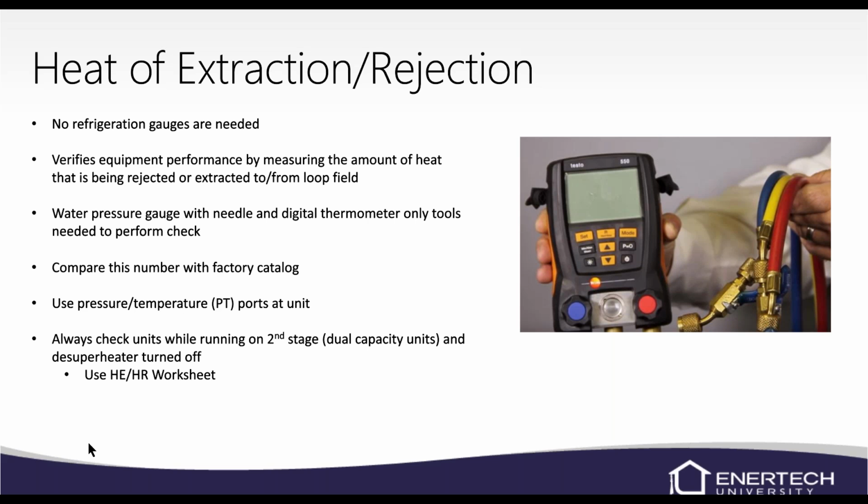With a pressurized system, it's sealed. So the only way to know is by using the IOM and looking at pressure drop. So make sure your installers are always installing pressure temperature ports. If you've got a water-to-water unit, make sure they're on the load and the source water lines, because we're going to have to check water flow on the load as well.